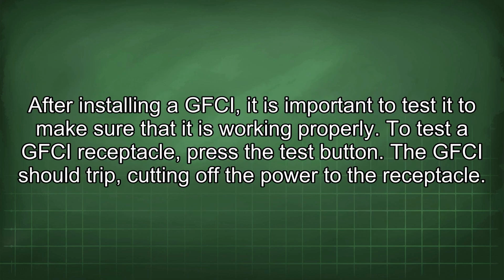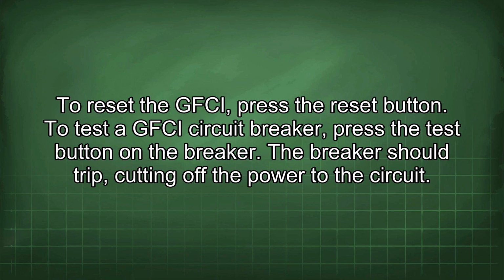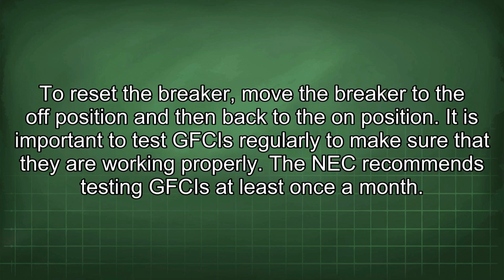After installing a GFCI, it is important to test it to make sure that it is working properly. To test a GFCI receptacle, press the test button. The GFCI should trip, cutting off the power to the receptacle. To reset the GFCI, press the reset button. To test a GFCI circuit breaker, press the test button on the breaker. The breaker should trip, cutting off the power to the circuit. To reset the breaker, move the breaker to the off position and then back to the on position.